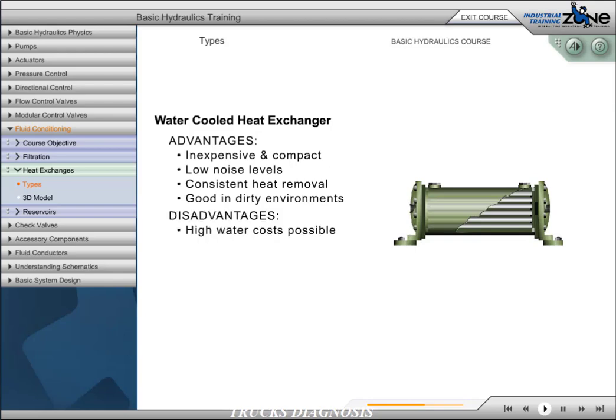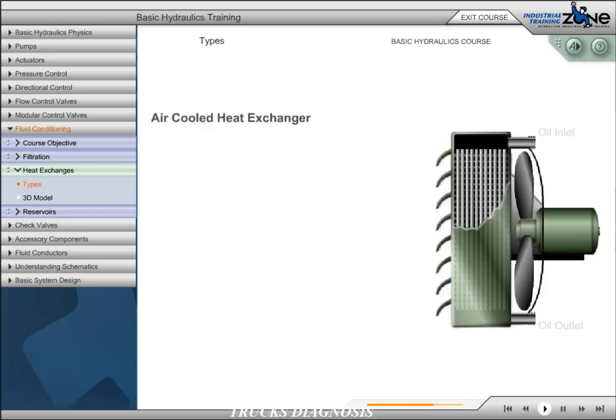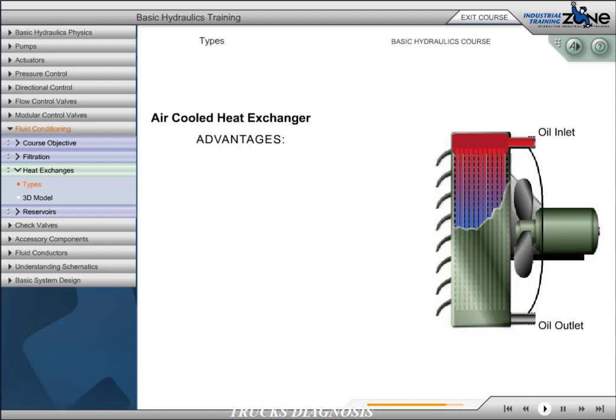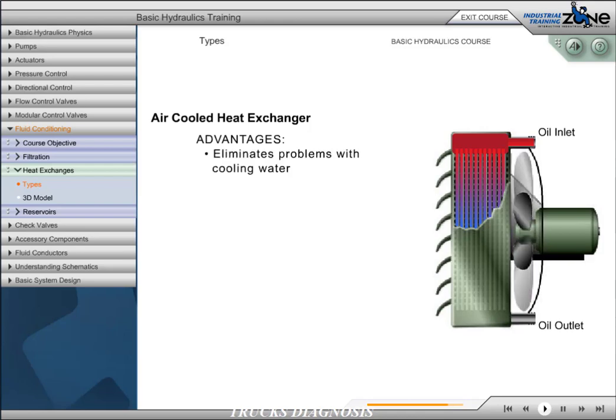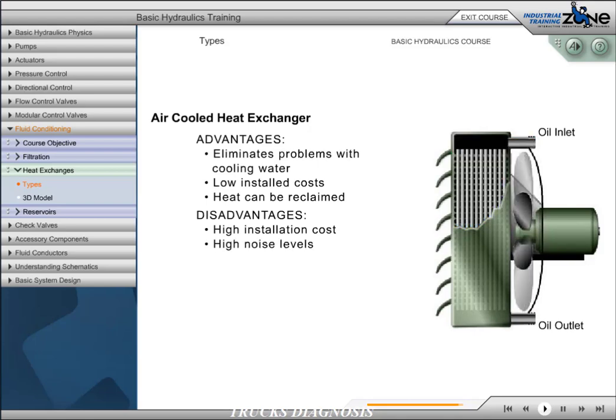The disadvantages of water-cooled heat exchangers are: water costs can be expensive, with rupture oil and water may mix, and they usually require regular maintenance from mineral buildup. Air-cooled heat exchangers consist of a steel radiator core through which oil flows while a strong blast of air passes across the core. In industrial applications, the air is pushed by an electric motor-driven fan. The advantages are: they eliminate problems associated with cooling water, they have low installed costs, and the dissipated heat can be reclaimed. The disadvantages are a higher installation cost, noise levels ranging from 60 to 90 decibels, and they are larger in size than comparable water-cooled equipment.